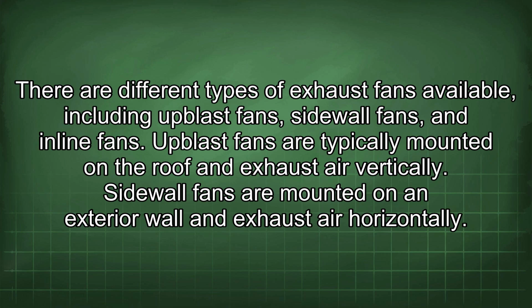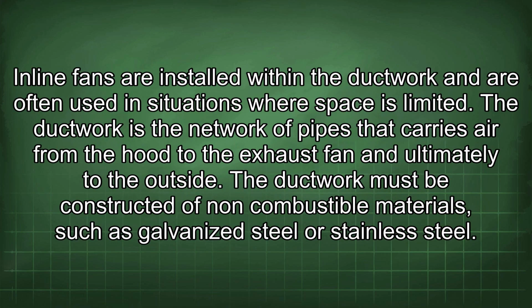Upblast fans are typically mounted on the roof and exhaust air vertically. Sidewall fans are mounted on an exterior wall and exhaust air horizontally. Inline fans are installed within the ductwork and are often used in situations where space is limited.